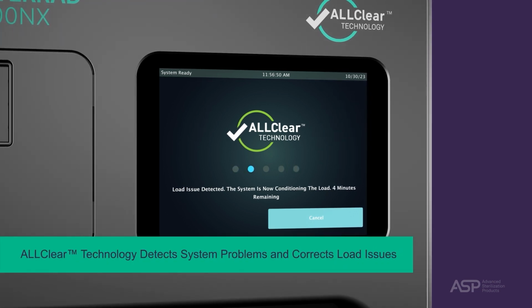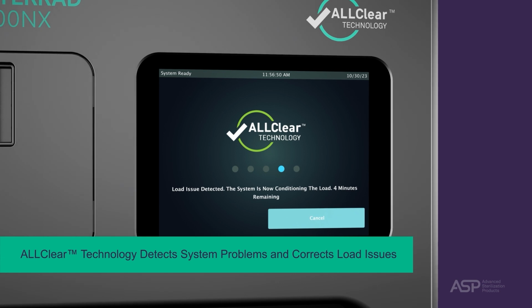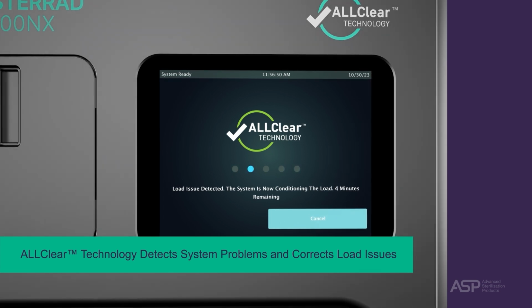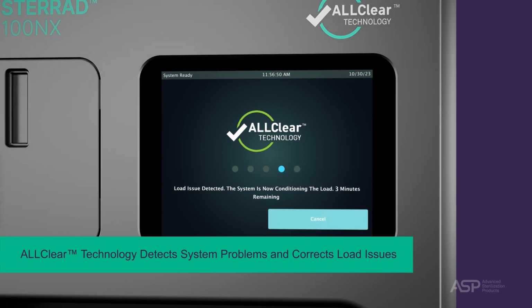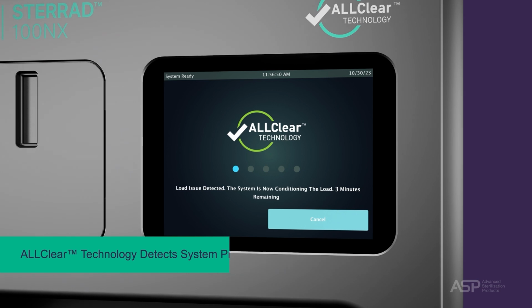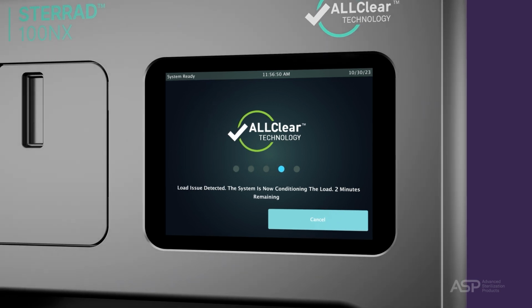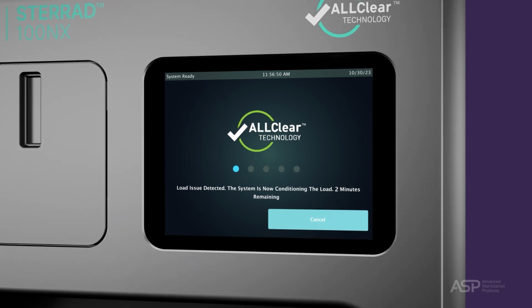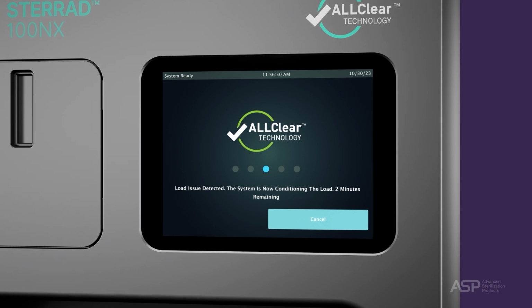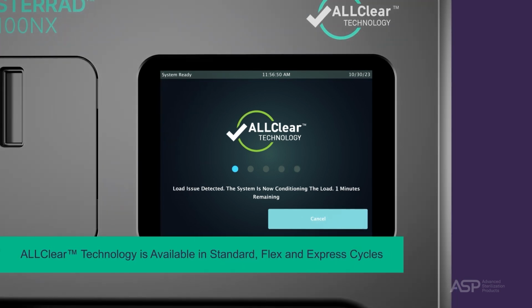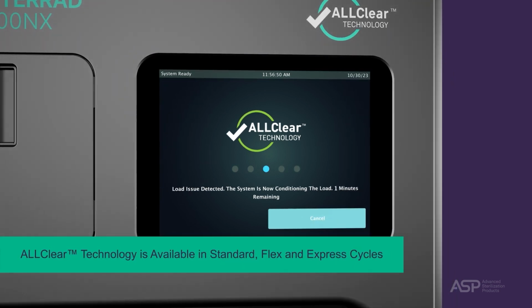If ALLClear technology cannot correct the issue, the selected sterilization cycle will not be started and a notification will be displayed on the screen. By utilizing the ALLClear technology, problems with a load can be detected prior to the hydrogen peroxide being injected. The ALLClear technology is available in the standard, flex, and express cycles.